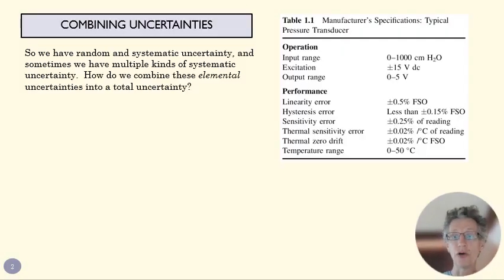So all of those uncertainties that we've talked about, whether big picture random or systematic, or smaller picture like linearity and hysteresis error and so forth that you can see listed on these manufacturer specifications, are called elemental errors. They're single errors that we calculate one at a time. Now what we're going to do is combine those elemental errors into a total uncertainty.